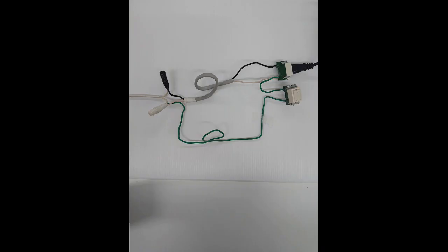First, we will explain how to measure leakage electricity using an actual electrical circuit. The photo is an electric circuit I made for an experiment. The left side is the power supply side, where electricity is sent from the outlet. In the actual site, this location will be the transformer. The right side will be the load side where the lighting equipment is attached. Electricity flows from left to right, passes through the load, and returns from right to left.